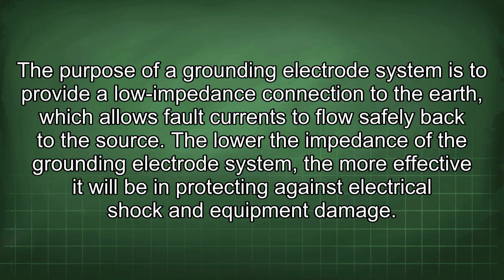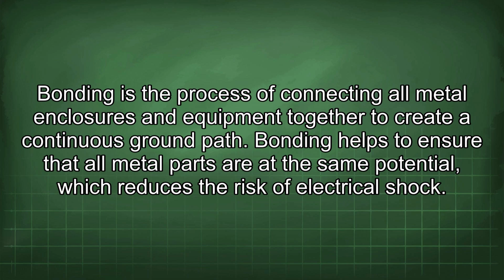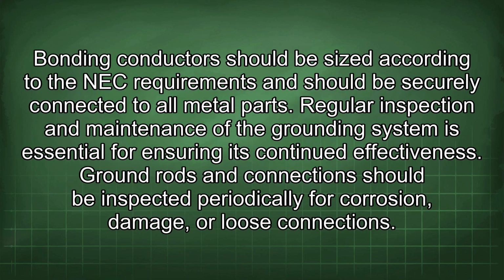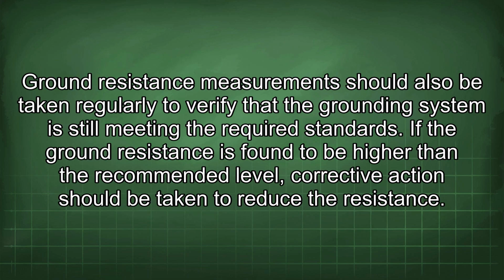The lower the impedance of the grounding electrode system, the more effective it will be in protecting against electrical shock and equipment damage. Bonding is the process of connecting all metal enclosures and equipment together to create a continuous ground path. Bonding helps to ensure that all metal parts are at the same potential, which reduces the risk of electrical shock. Bonding conductors should be sized according to the NEC requirements and should be securely connected to all metal parts. Regular inspection and maintenance of the grounding system is essential for ensuring its continued effectiveness. Ground rods and connections should be inspected periodically for corrosion, damage, or loose connections. Ground resistance measurements should also be taken regularly to verify that the grounding system is still meeting the required standards.